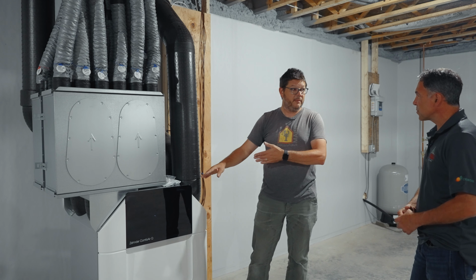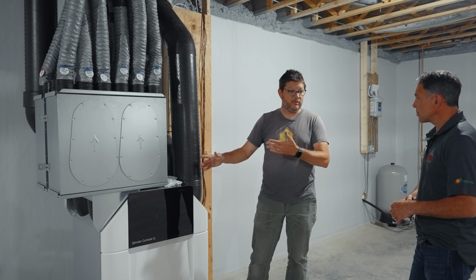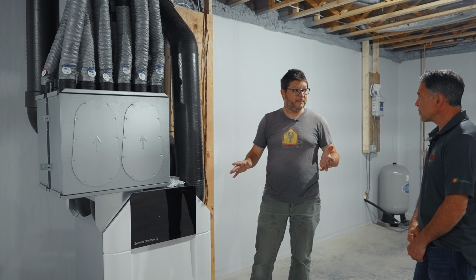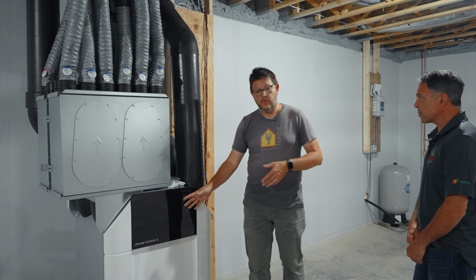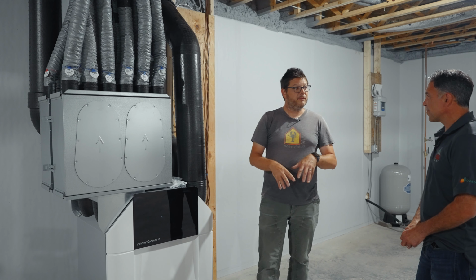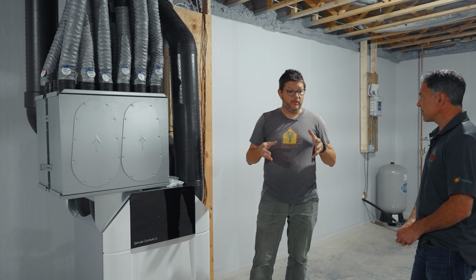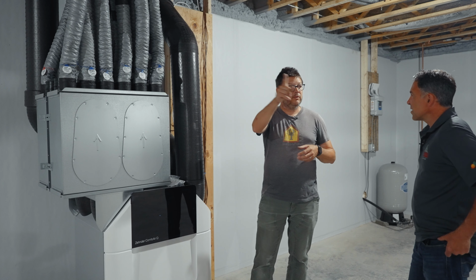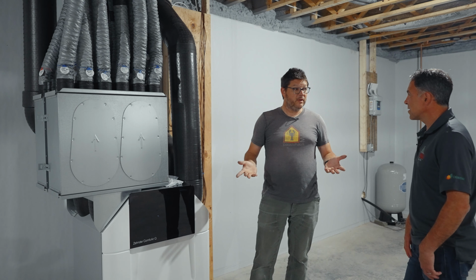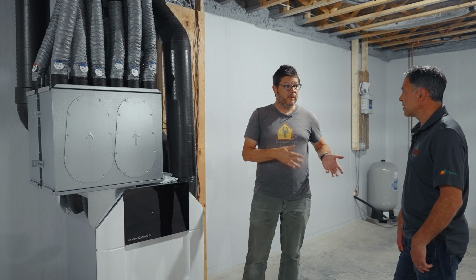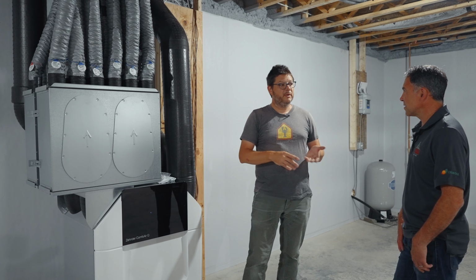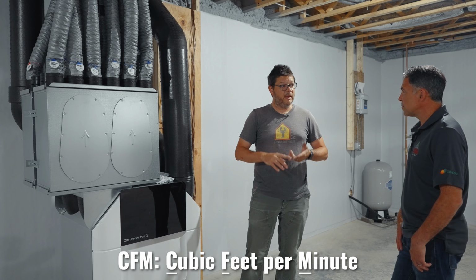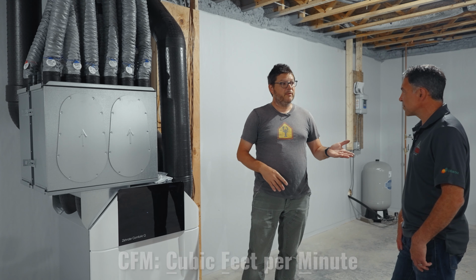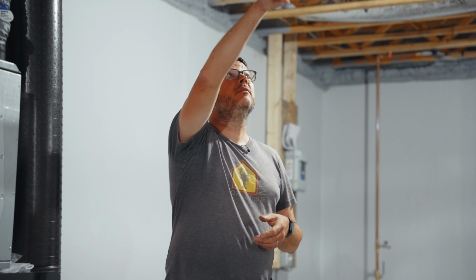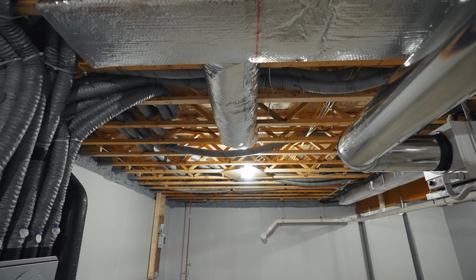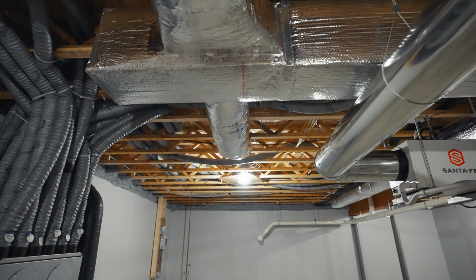A technician from the manufacturer came down and spent 3 hours and they commissioned the whole system, which basically means they go into the control board here, they dial it into the specific house, and they take a flow hood and they go to every single register in the house. Because when you engineer airflow, every room, just like with heating and cooling, every room needs a certain number of CFM of air in order to maintain that comfort. And when you design ductwork like this, these are smaller ducts and the larger ducts, because that's a much bigger fan motor in there.